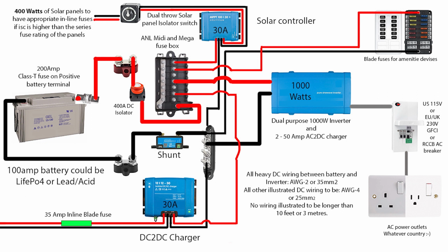Please note, it's sensible not to try and use an inverter running solely from an off-grid power source like solar panels or a wind turbine or a vehicle or boat engine alternator. It's always best to have some kind of battery or batteries as an intermediary power source, as an inverter works better with a fairly stable DC power input. So, if there is a drop in the DC input power, like a cloud passing over the solar panels, or an ebb in the wind pushing the wind turbines, then an intermediary power source like a leisure battery will compensate for that momentary drop in power and maintain a consistent and stable flow of DC power to the inverter.